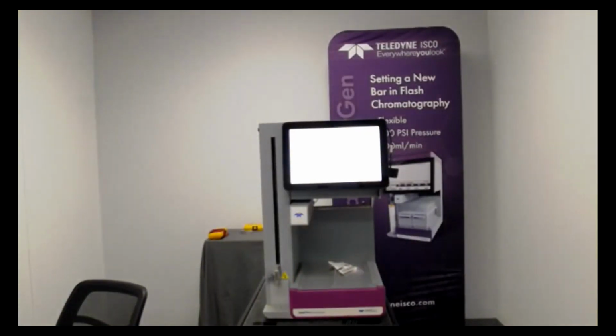Just on the lamp there in the service menu, I found that when you turn the lamp off, I can see that the energy drops. Oh yeah. But when I try and turn it back on in there, it doesn't respond. I have to reset the instrument and then the lamp will come back on. Interesting. I don't usually have that problem, but I can look into that for you. I'm gonna make a note on that one. Okay.